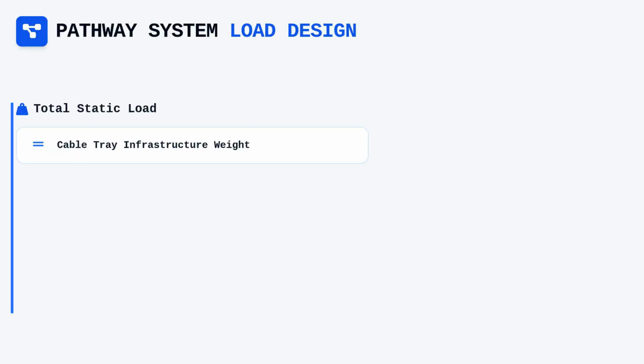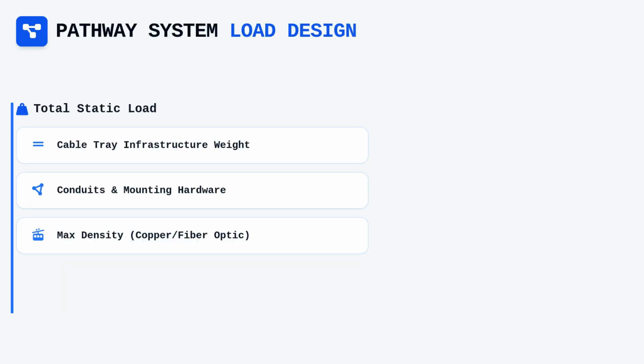When we approach the design of a pathway system, we must first account for the total static load imposed by the infrastructure. This involves summing the weight of the cable tray, the conduits, and the maximum design density of the copper or fiber optic cables themselves. It is a common mistake to calculate based on empty tray weight, yet real-world scenarios demand that we design for the maximum capacity of the pathway when it is fully populated.